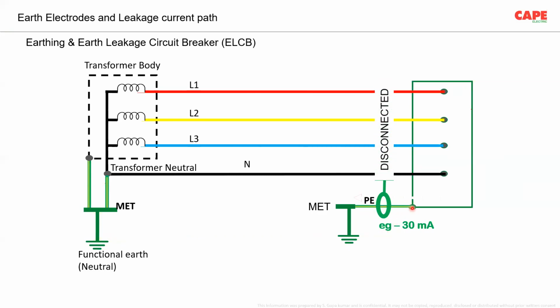Now, what you should understand is that in an ELCB, this earth wire and the earth connection to the earth electrode are very much important. If we miss this particular connection, then we are in trouble, because there is no current flow to the earth electrode, and if a person touches, he gets a shock. So this is a dangerous situation. Now imagine the ELCB is not working, there is a leakage, and a person touching, he will die, because the ELCB must trip by sensing this particular current. And in case of any change in this sensing of this particular current, there is a trouble. The earth electrode and this connection are very much necessary.